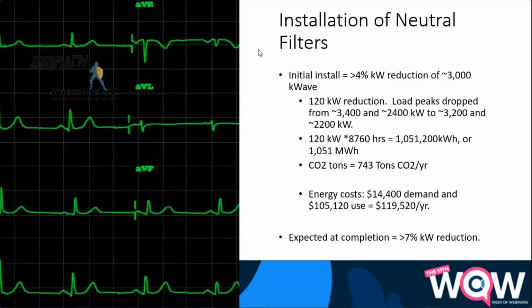We took a look there. They had a lot of grounding issues. They were going through bearings relatively quickly. They had unbalanced neutral circuits and a lot of neutral harmonics. We estimated, by the way, the end result wasn't 7%, it was 14.5%. But if we just look at a 4% reduction in energy as a direct result of getting rid of the harmonics. Oh, by the way, let me go back to that. That was by putting in harmonic filters, because they had already put in power factor correction. The power factor correction, when I have a high harmonic condition, actually generates more energy consumption, not less.